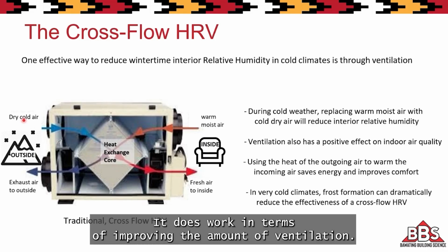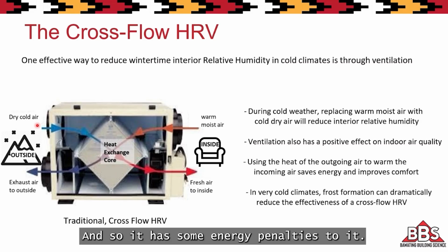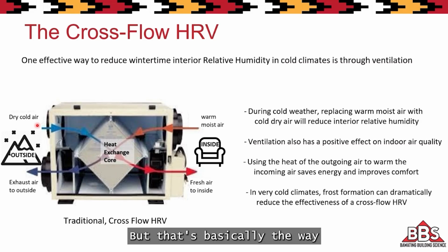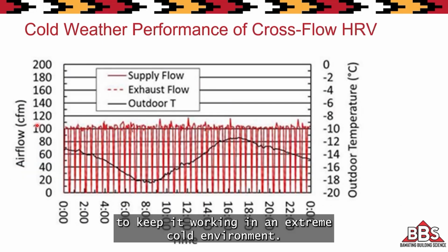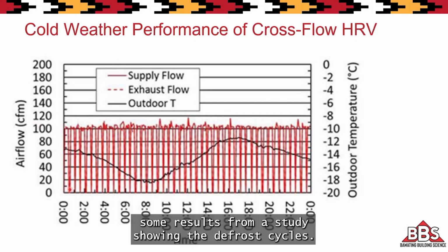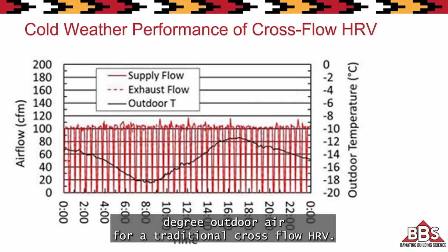It does work in terms of improving the amount of ventilation. It also reduces the heat exchange, and has some energy penalties to it. But that's basically the way to keep it working in an extreme cold environment. This is just some results from a study showing the defrost cycles, I believe at minus 20 degree outdoor air, for a traditional cross-flow HRV.